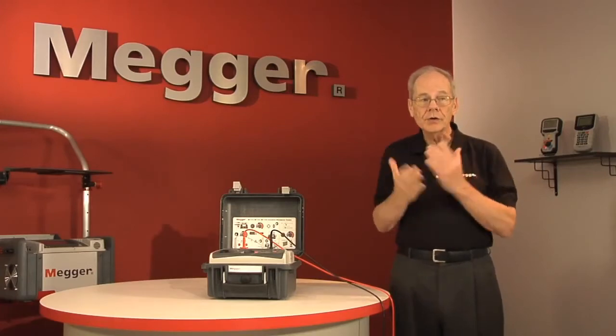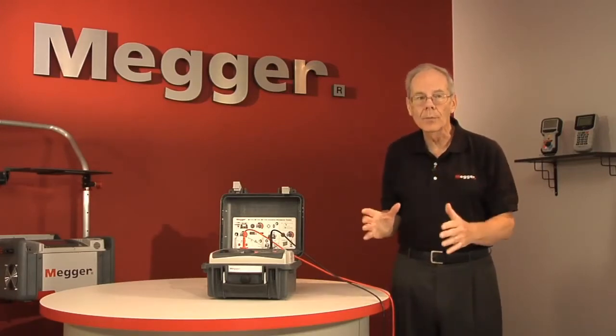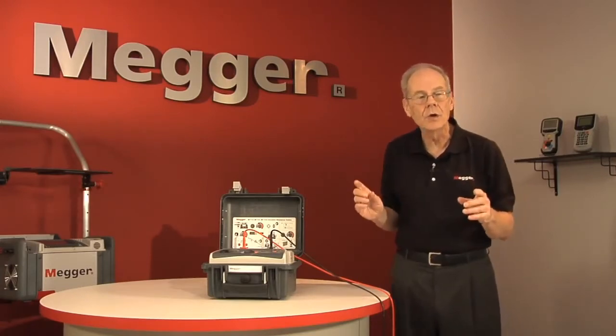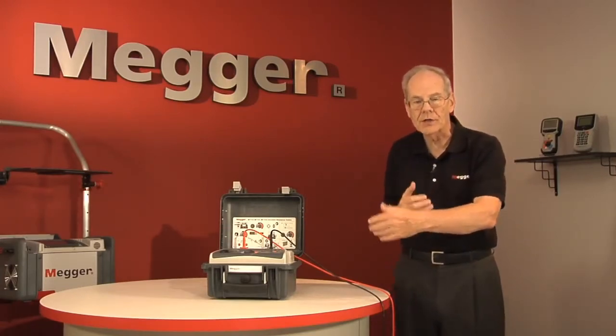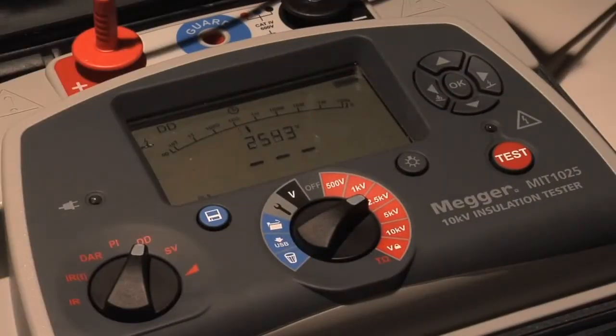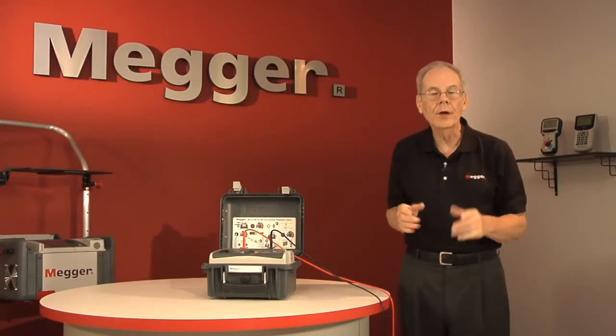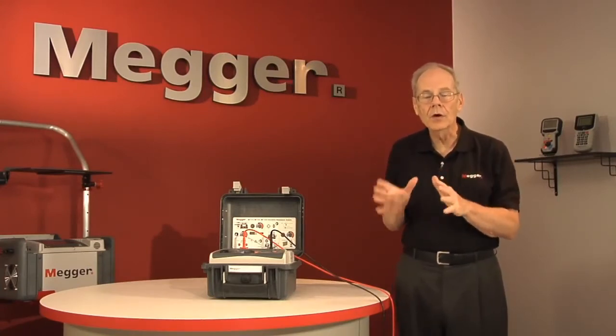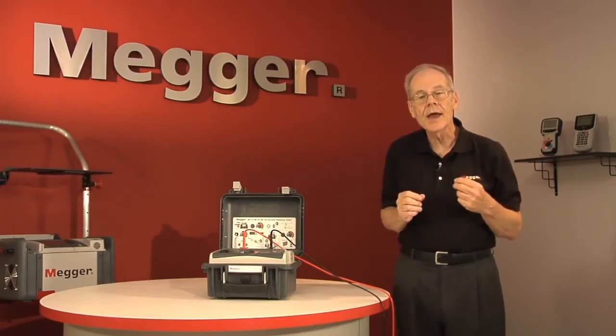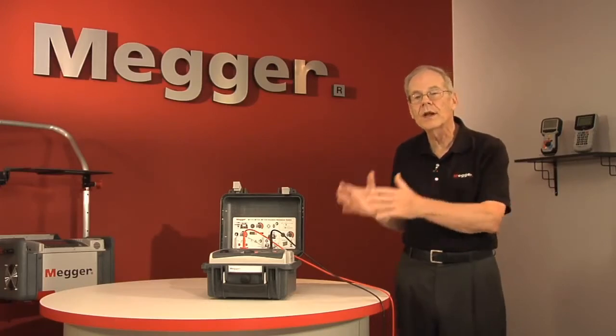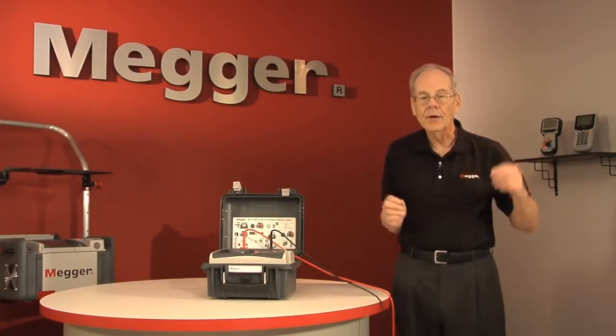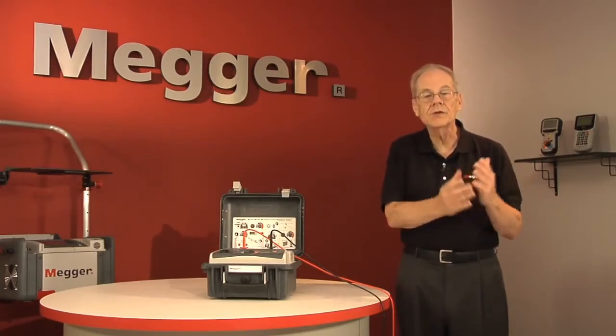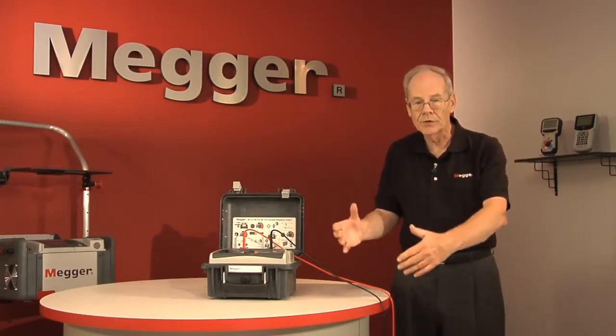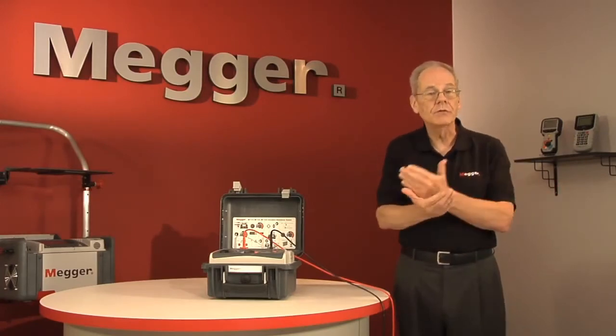When you're doing the dielectric discharge test, you're now actually incorporating the discharge current into the evaluation of the test. So what happens is, test runs for 30 minutes. The idea behind that is almost all test equipment is going to be pretty close to full charge at the end of 30 minutes. At that point, the test voltage shuts off. We no longer have an applied test voltage, but the tester now begins to measure what is sometimes called relaxation current, which is that all the current stored on the test item is now going to try to relax and return to its original state in the absence of applied voltage.